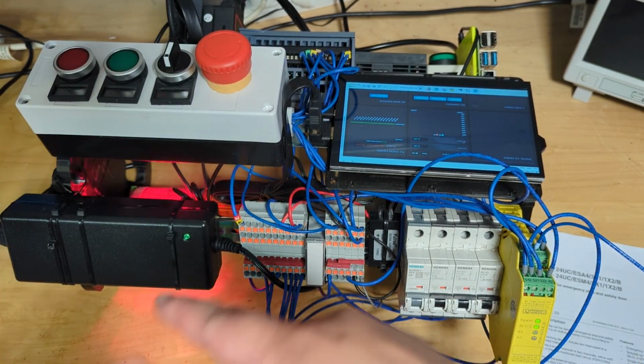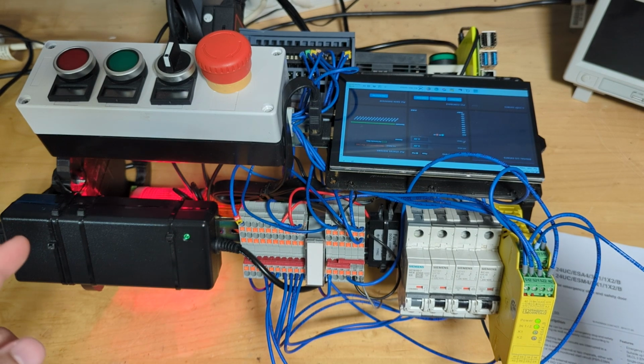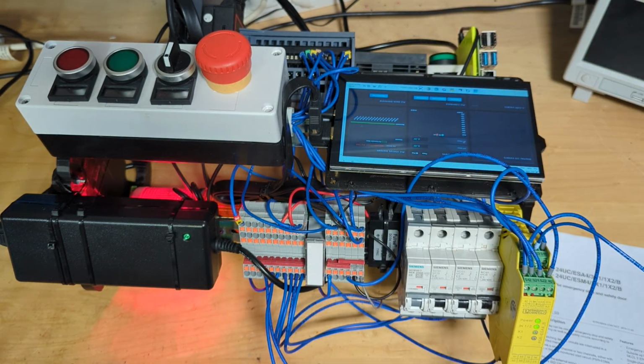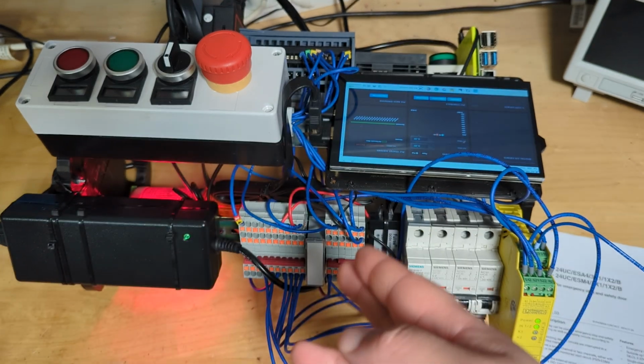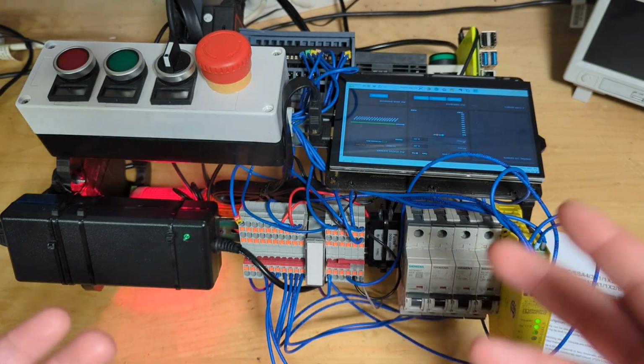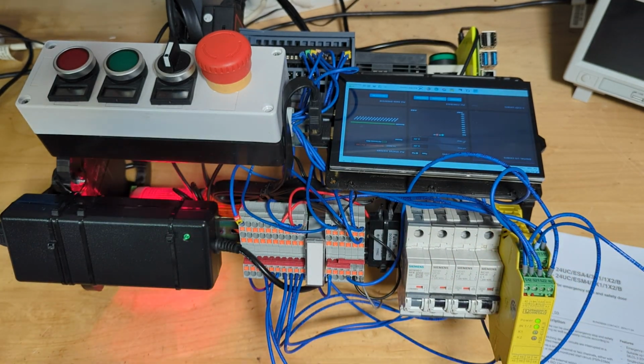The problem with that is that if you've got 7, 8, 10, 12, 15, 100 e-stops daisy chained together and you hit e-stop number 6 or e-stop number 82 or whatever it is, you just lose power and you have no idea what e-stop's been pressed. You'd have to go around and check all the e-stops. If the wires come off or got corroded and it's no longer making a good connection, you're just gonna have to debug hundreds of meters of wire.